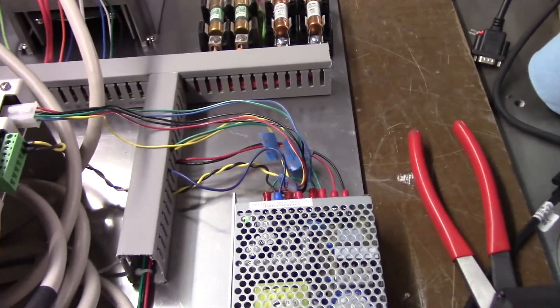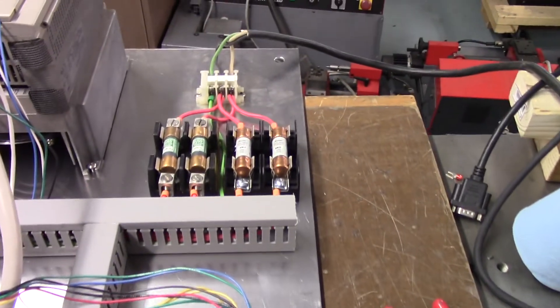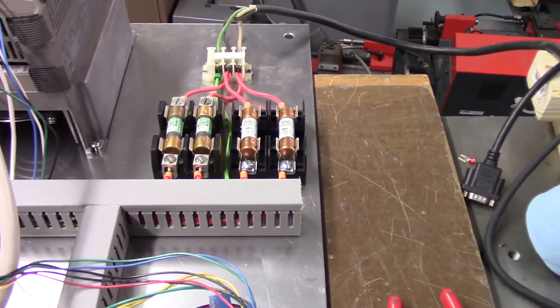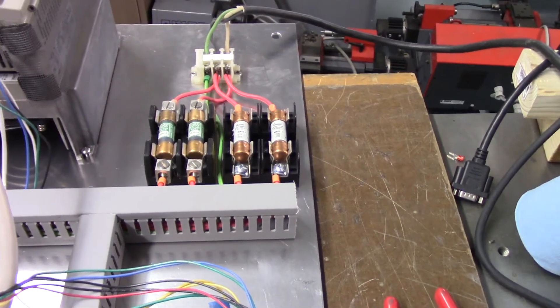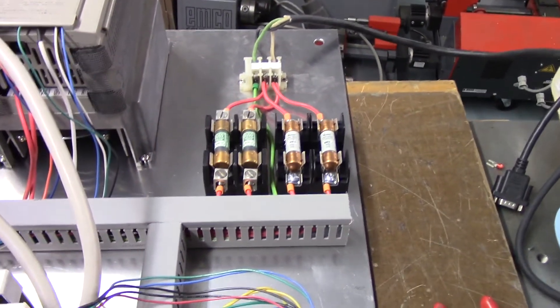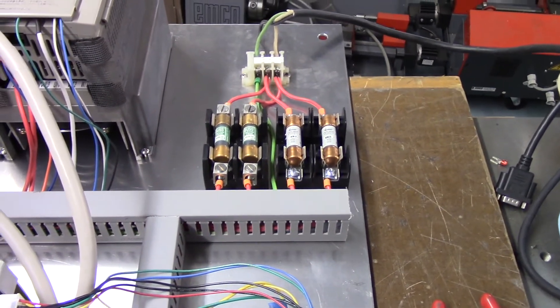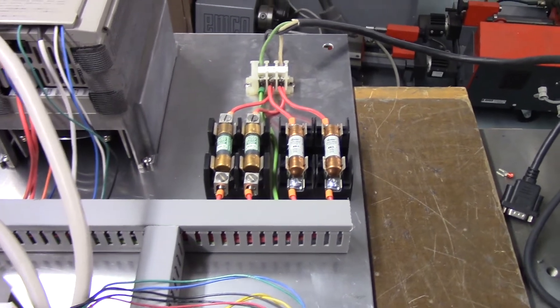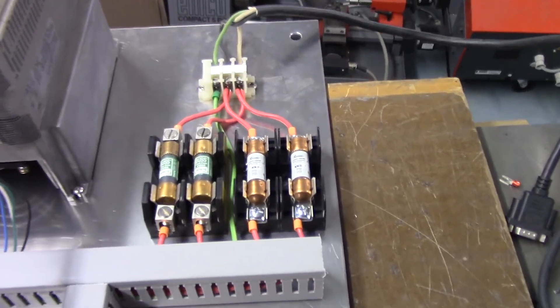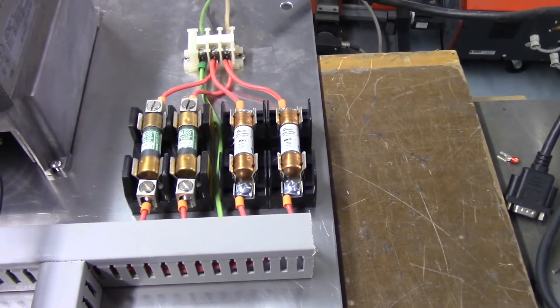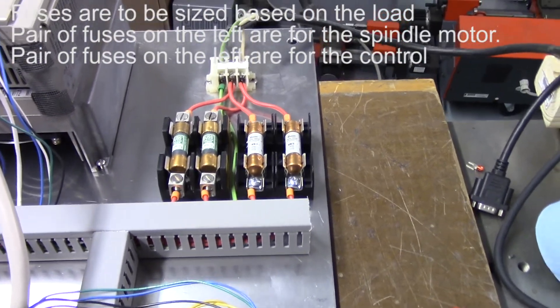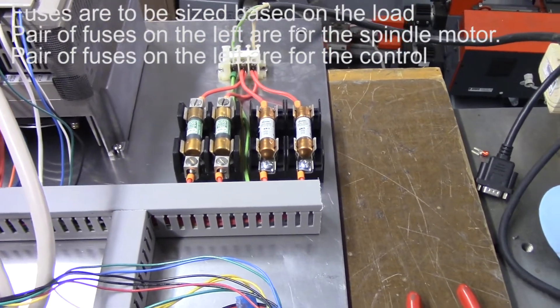That's pretty much it. I tend to use fuses versus breakers - to each his own on that one. I use fuses, typical 30 amp 250 volt fuses you can get at the home center. I don't use anything that you can't get locally, but fuses tend to react more quickly than a cheap breaker. It's basically a testament to all the work we did to get the DYN4 AC servos to work with Centroid. This isn't on a machine yet, so I'll be installing Oak and three DYN4 drives and their AC motors on a Fadal TRM tool room mill in upcoming videos. I've got to build a panel for it. I'll do more in-depth videos on the installation there.